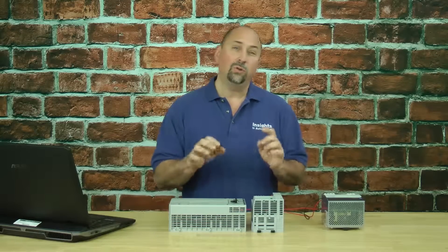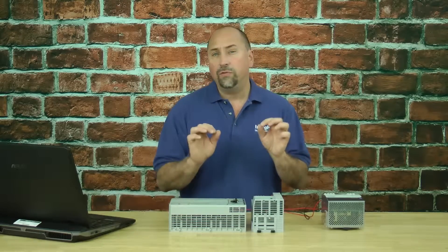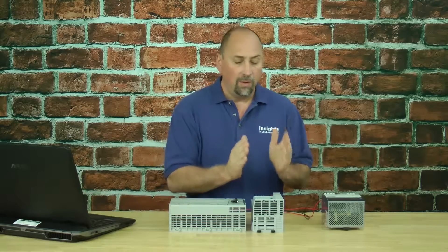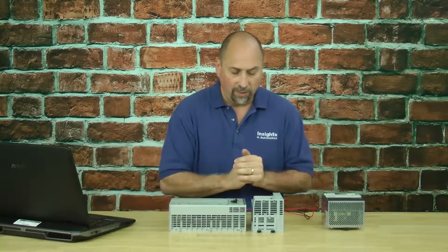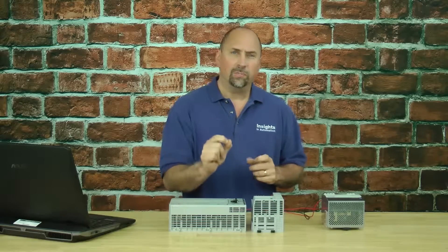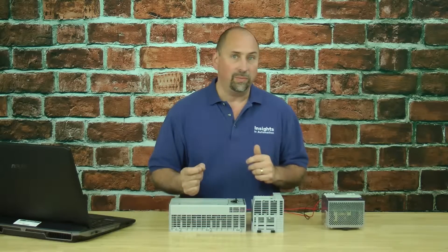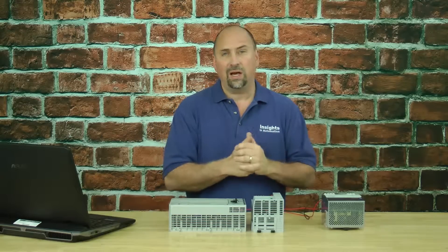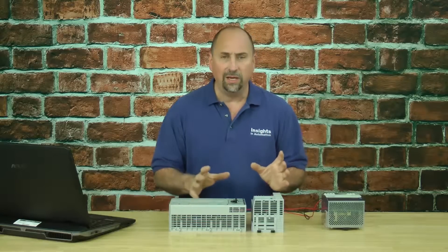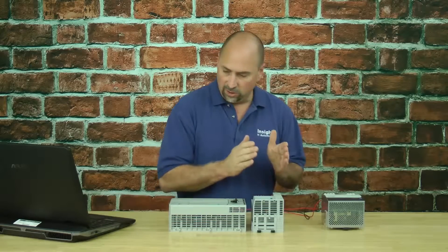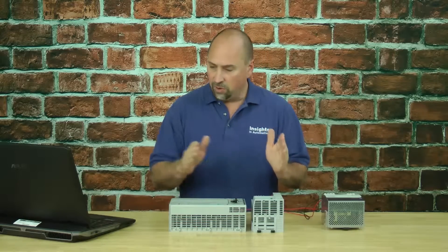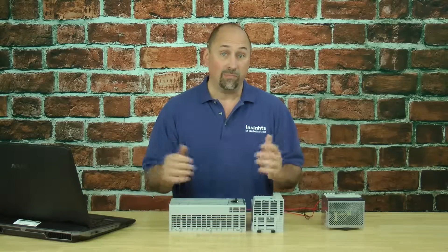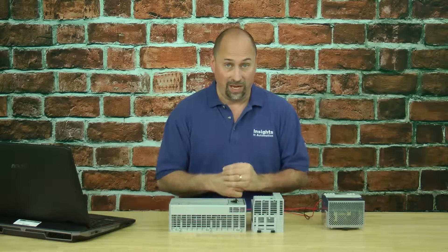As a second option, you can do it over Ethernet, but here's the thing: if you're going to flash over Ethernet, make sure you're on a one-to-one connection with the processor. I would typically recommend going through a switch because your computer will disconnect and reconnect from the Ethernet. Windows will disable and re-enable your Ethernet card when it sees the CompactLogix reboot. So again, if you're going to flash via Ethernet, I recommend that you use a switch and have only your laptop and the processor on the network at the same time.